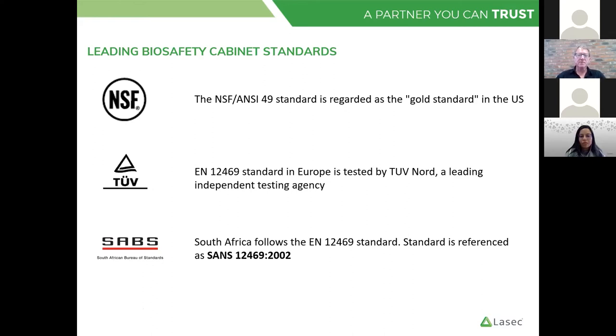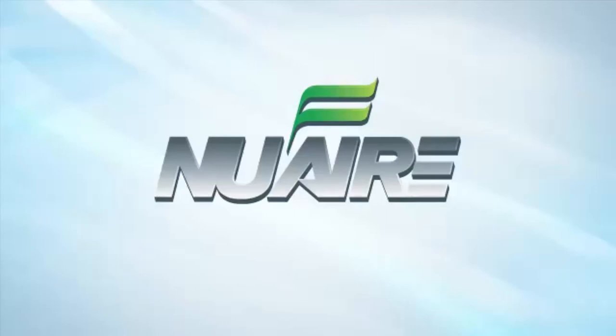There are various standards in the world used to certify cabinets. The cabinet itself is certified at the factory by one of these standards. We operate with all three, but generally for field certification — meaning an engineer goes on site and validates a cabinet — we operate to the NSF 49 standard, which is the gold standard in the world. It means that the person, not the company, who is coming to do the certification has been accredited and needs to be re-accredited on a regular basis, and is able to perform these tests and certify the cabinet on site.